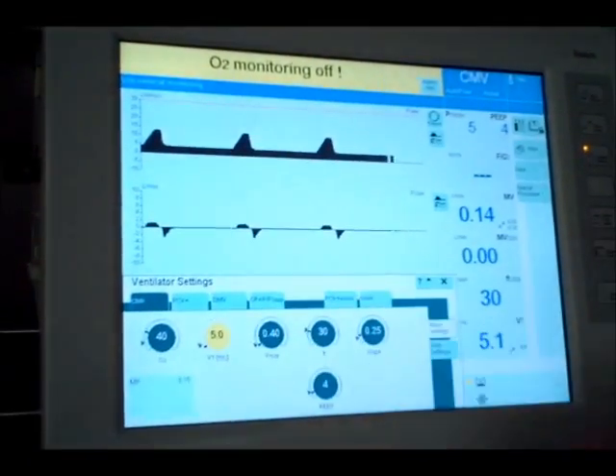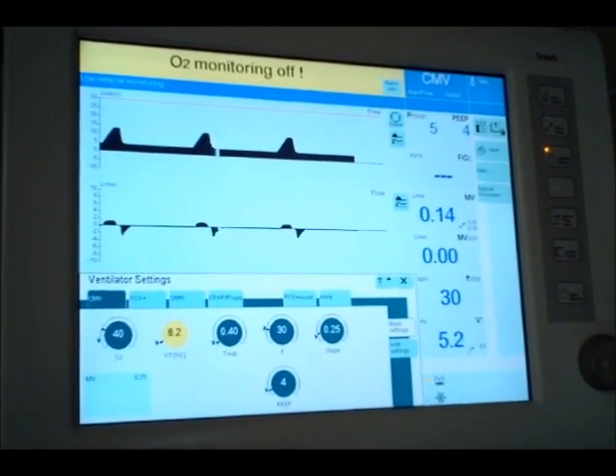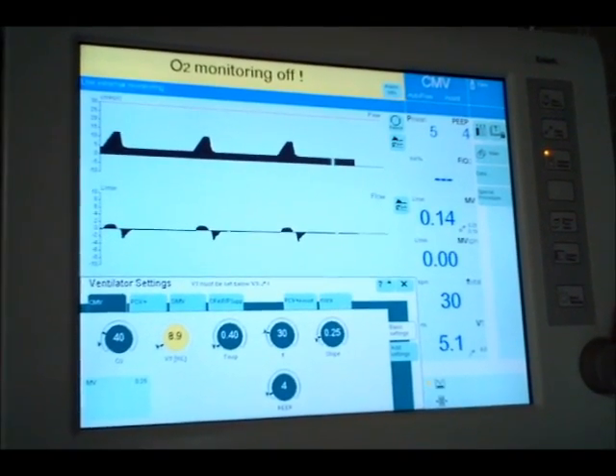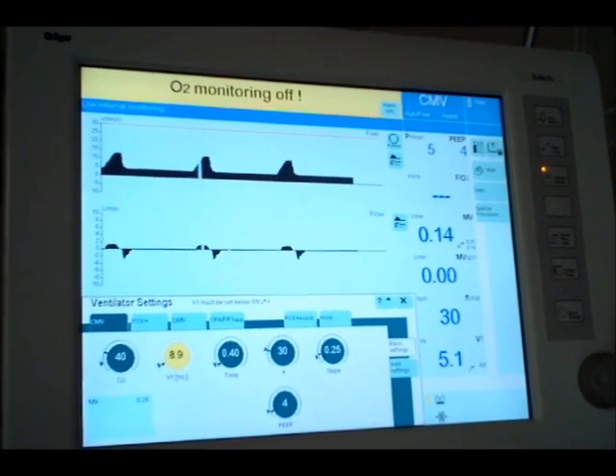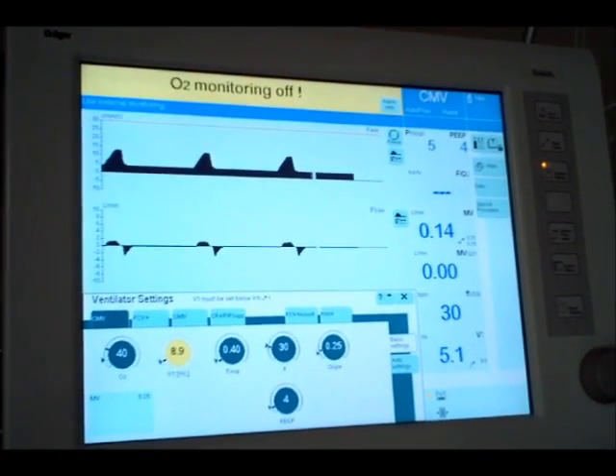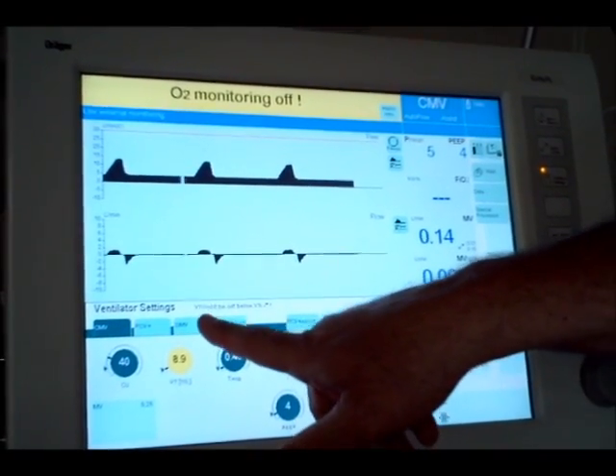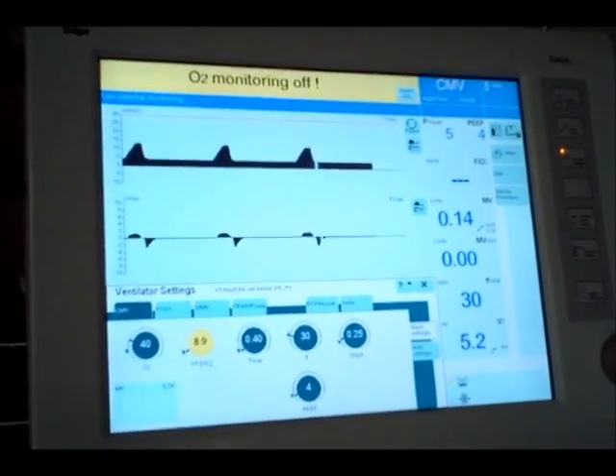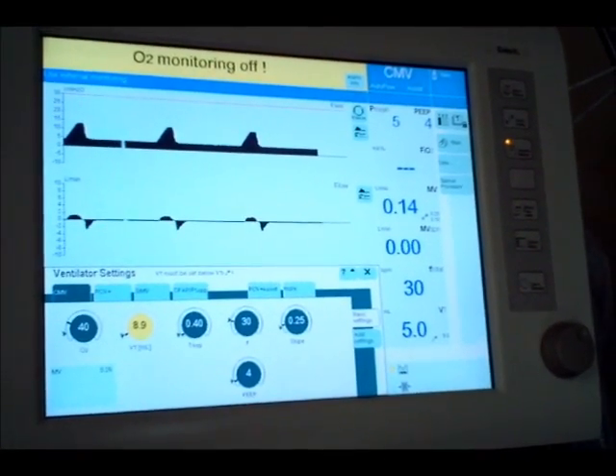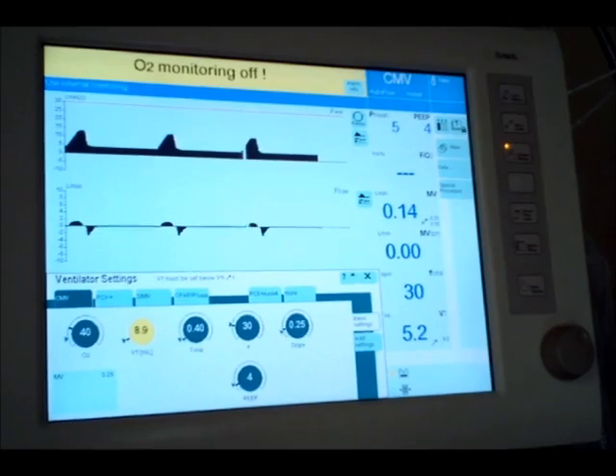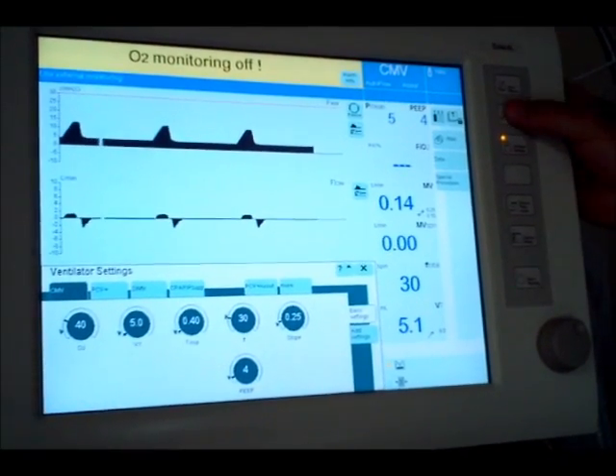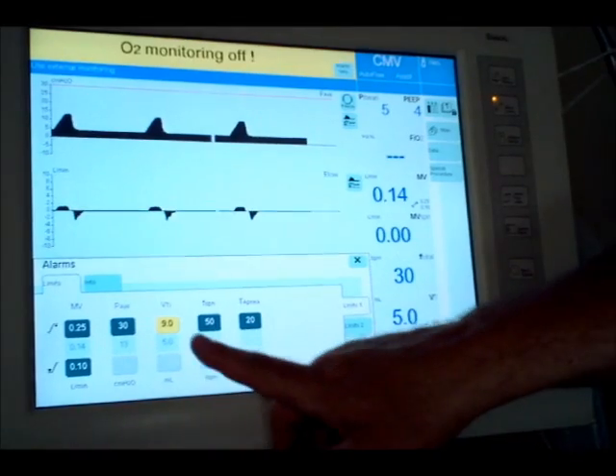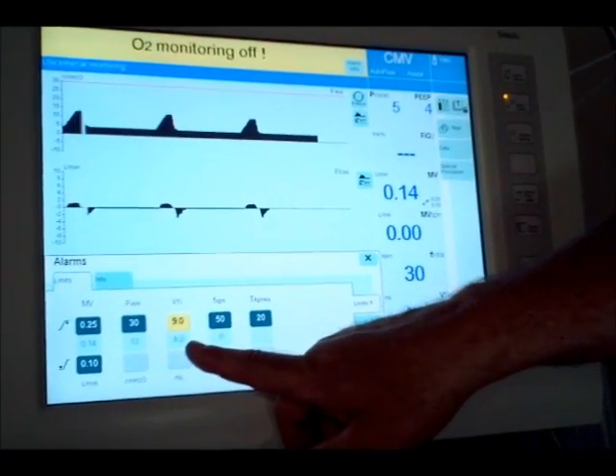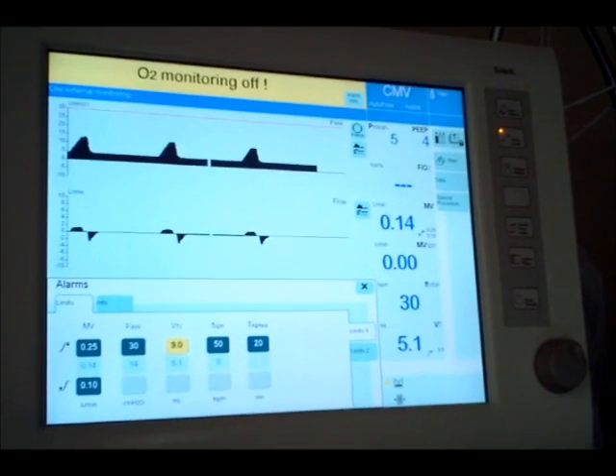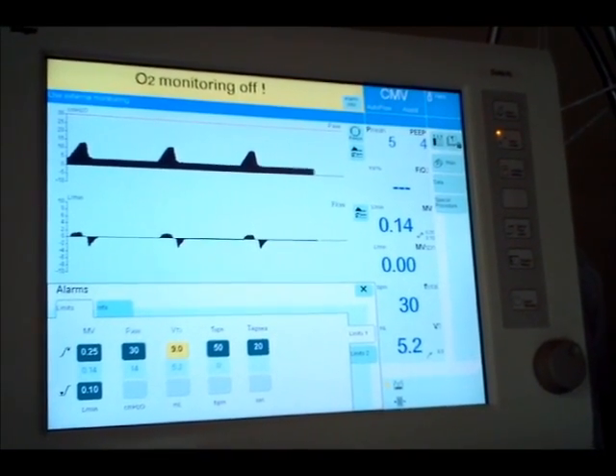All right, so what do I need to do? We're still in the same mode. Turn my tidal volume. Oh, I want to go. All right, so I get this little message here. It says, tidal volume must be set below my inspiratory tidal volume or my high tidal volume alarm. Okay, some of you ran into this during lab. So I have to go back in, change my alarm limit. So right now it wouldn't let me set my tidal volume higher than 9. Mark wanted 12. Good thing, because now we'll see some of the things that might come up during your checkoff.